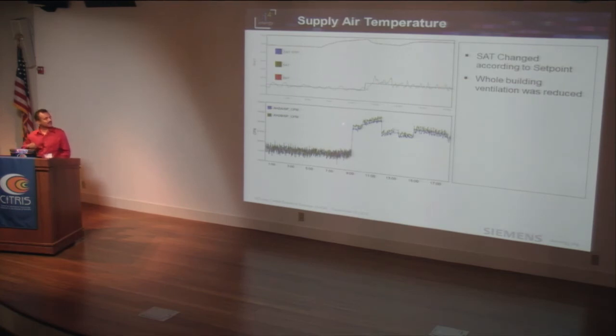With this, the ventilation rate in the building was high during the pre-cooling, and then during the DR period it was kind of low, and then it resumed here. You can also see the return air temperature, how it was during the pre-cooling, and also it was relaxed after some time.